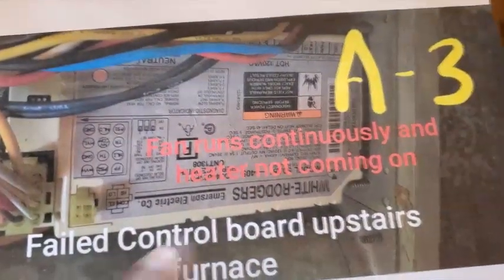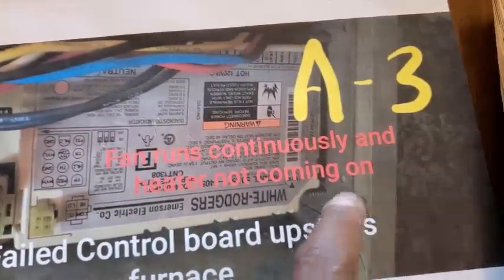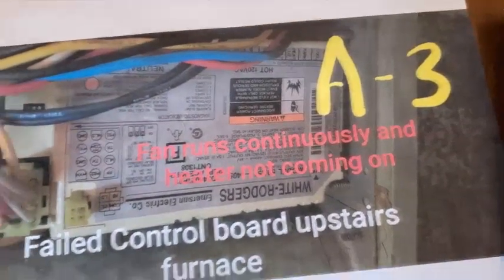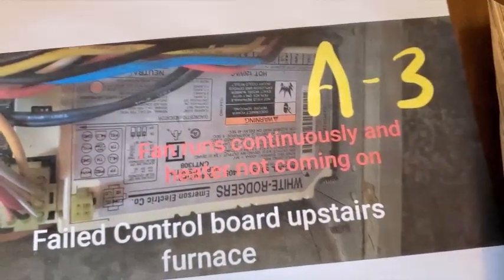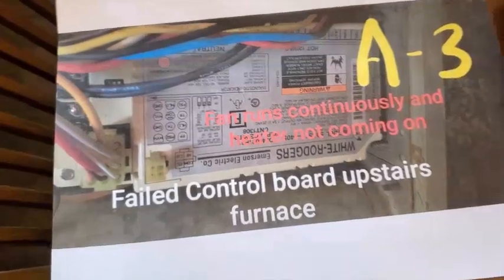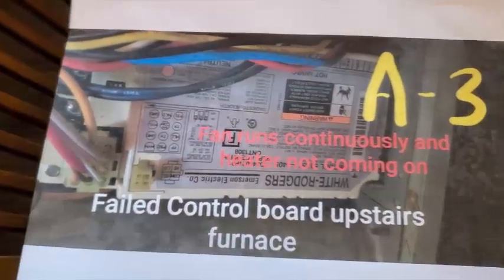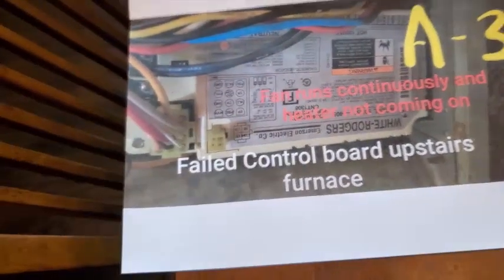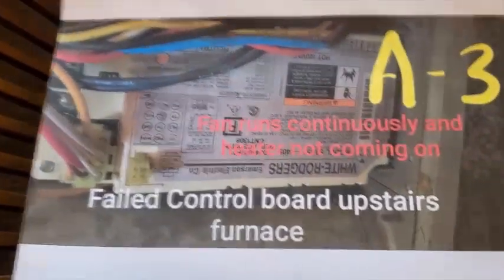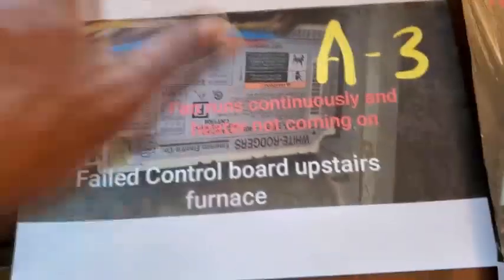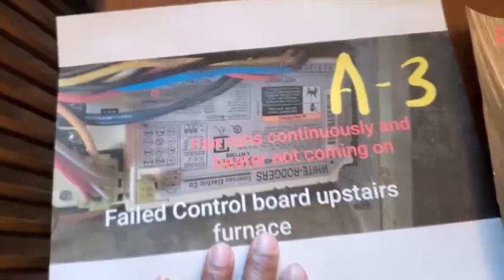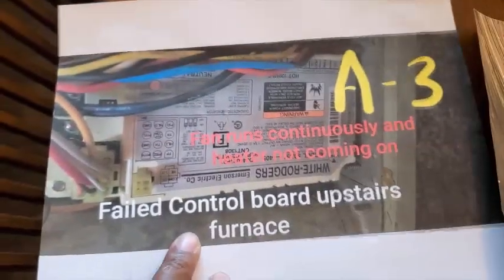As you can see, like A2, that's why diagnosing needs a new control board. I'm just telling them the fan runs continuously and the heater is not coming on. Without that control board, I really can't even troubleshoot the heat, because it could be a bad flame sensor, or anything going on with a pressure switch. But you've got to get this control board replaced before I can move along with that one.